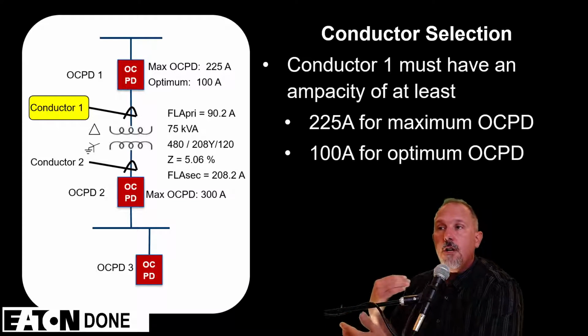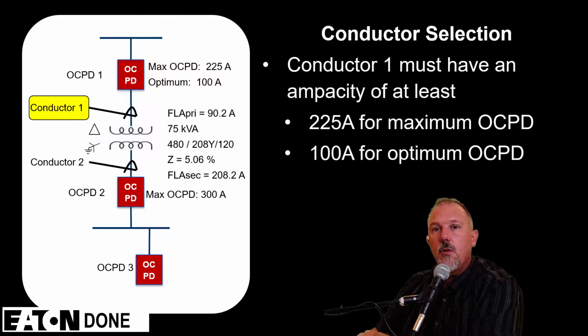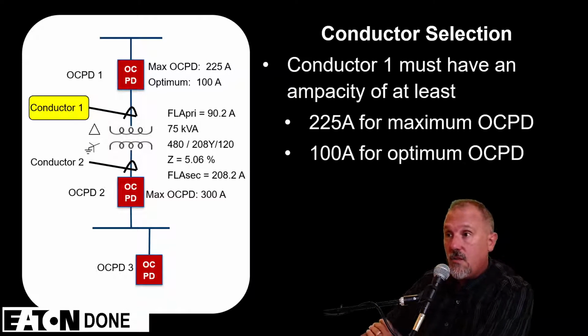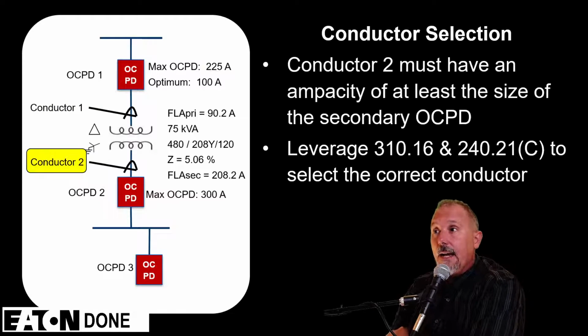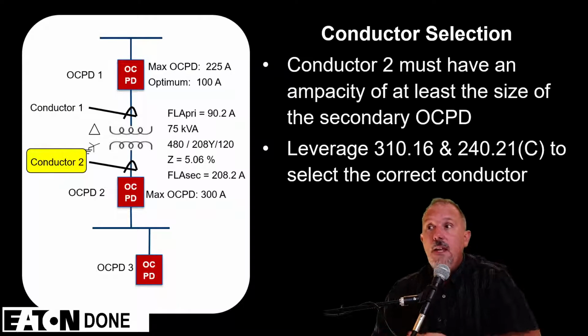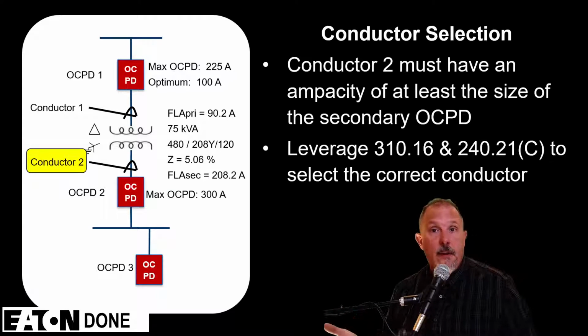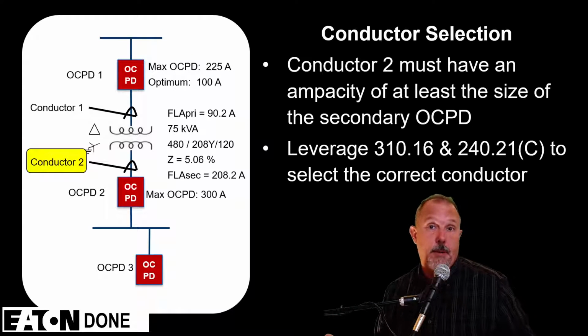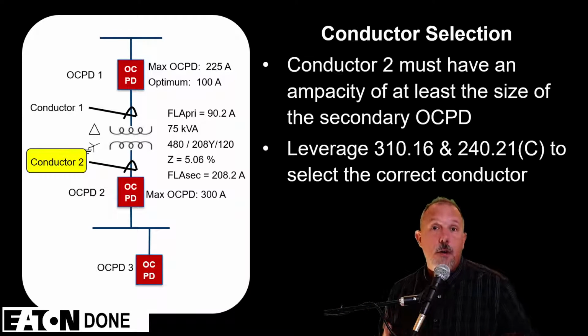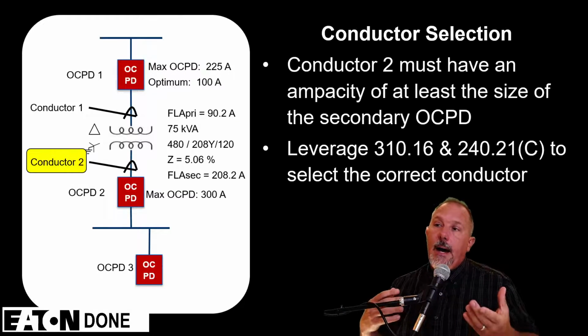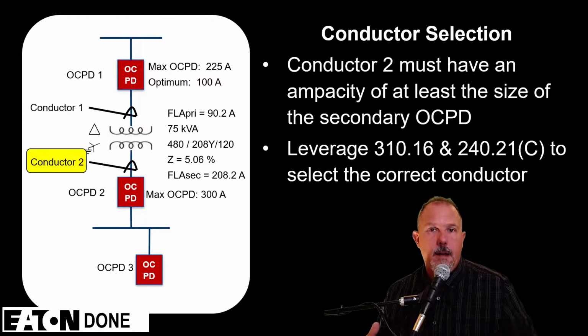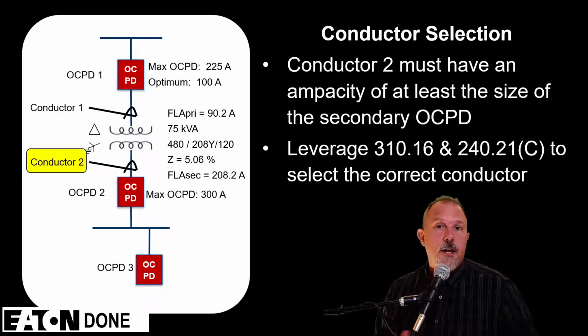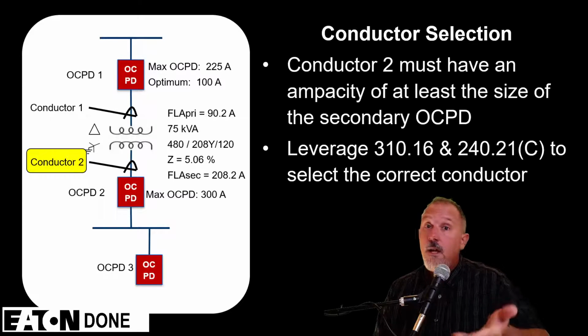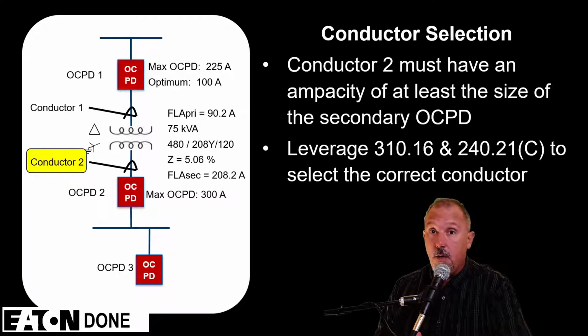All right. So your conductor is going to be driven by whatever circuit breaker or fuse you picked on the primary of that transformer. For the secondary, again, I can put a 300 amp panel board. I could also put a 100 amp panel board, a 150 amp panel board, or a 200 amp panel board. I can select anything less than 300 amps, and my conductor size is going to be based typically on the size of my overcurrent. Now, I could put a 200 amp panel board in there and put 300 amps worth of conductors. That limiting factor is going to be what the lugs can handle on your main breaker.